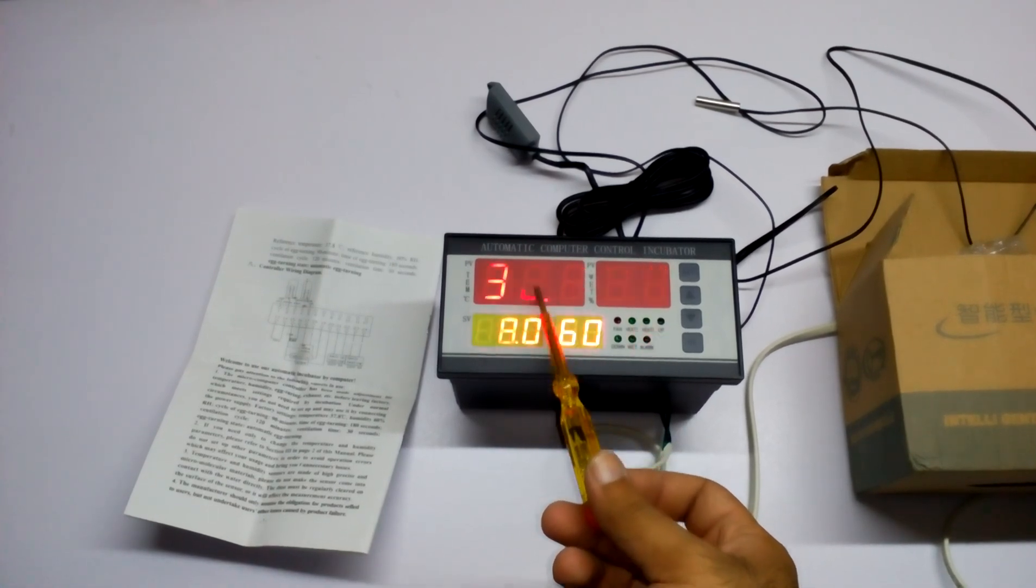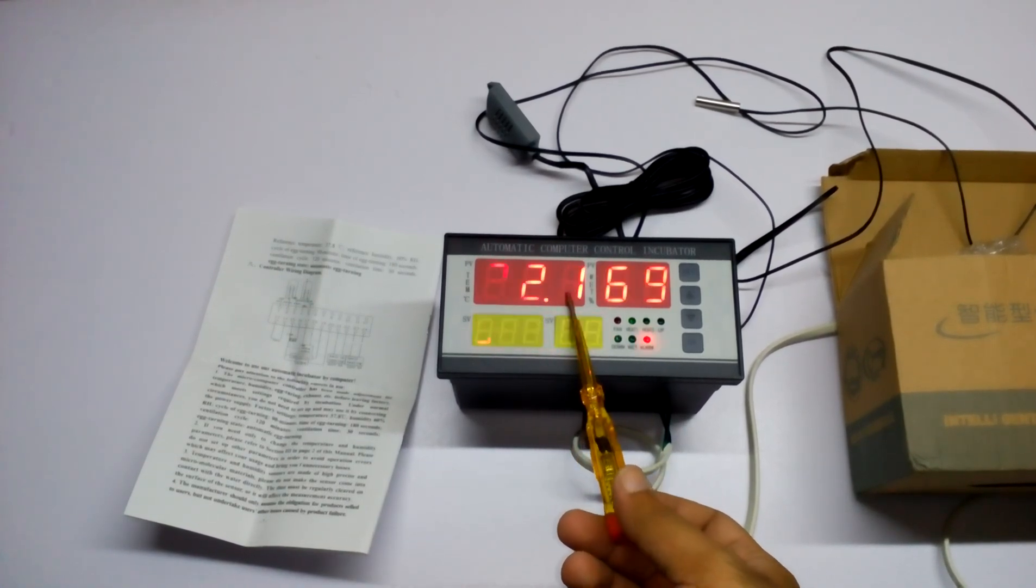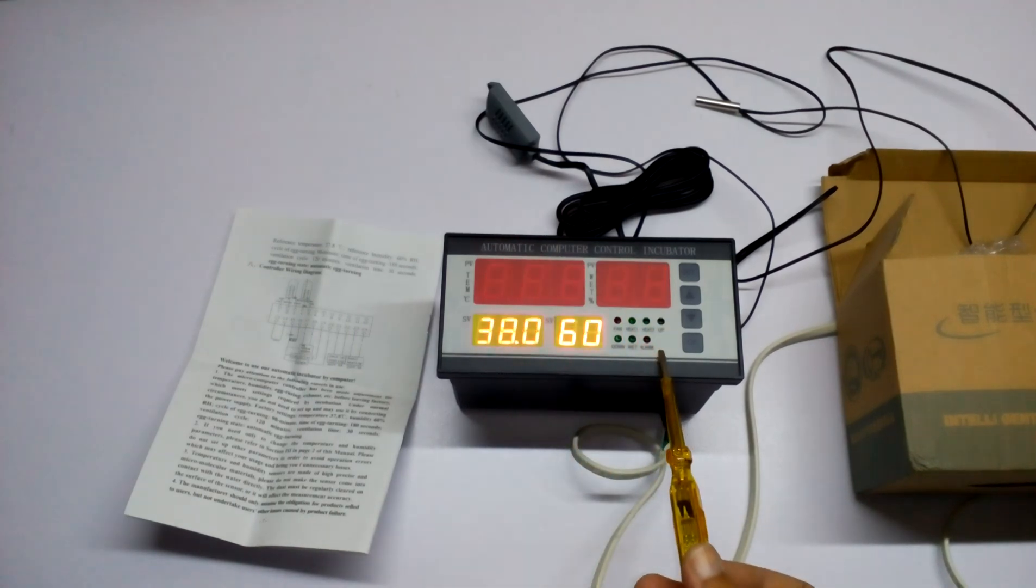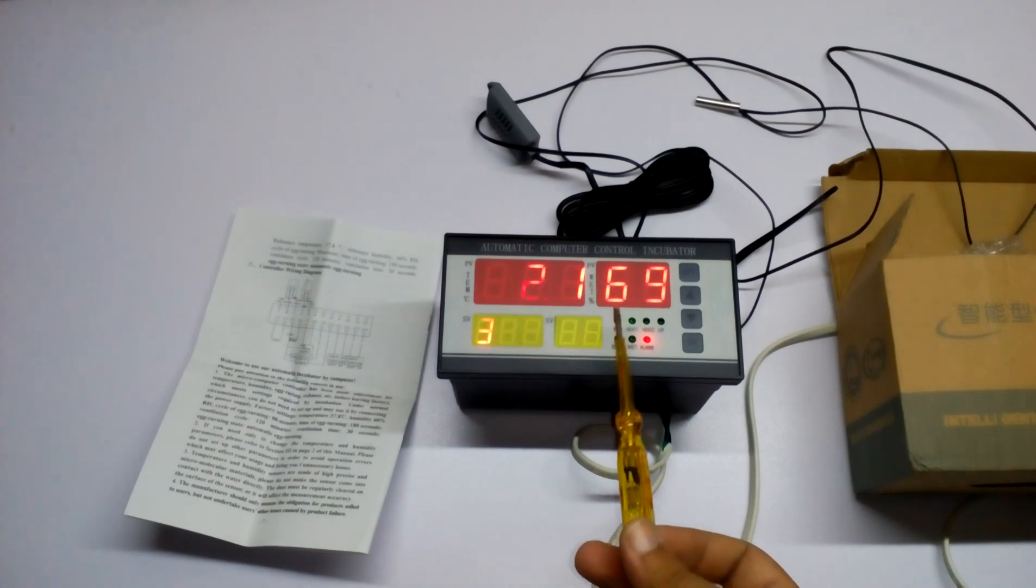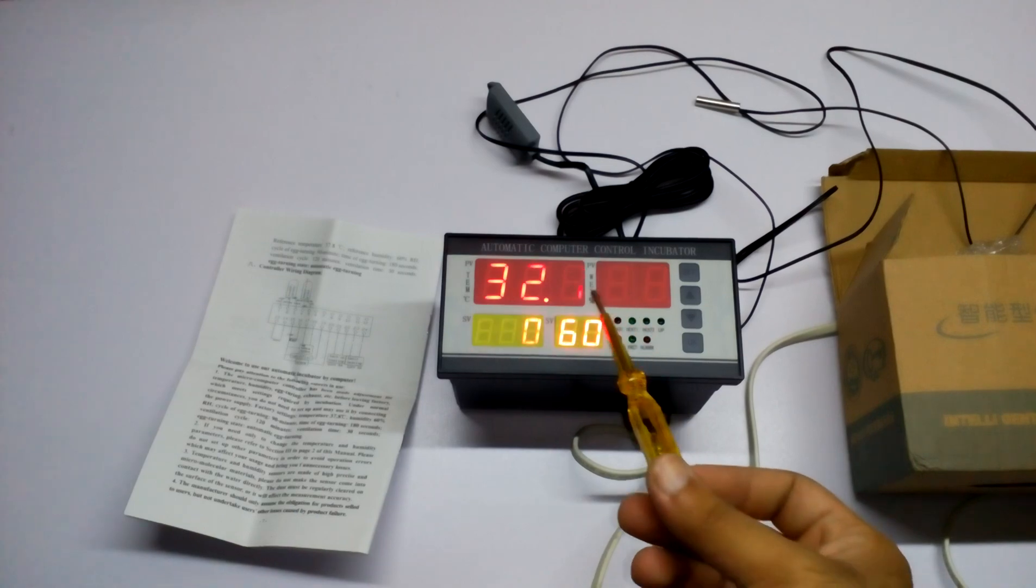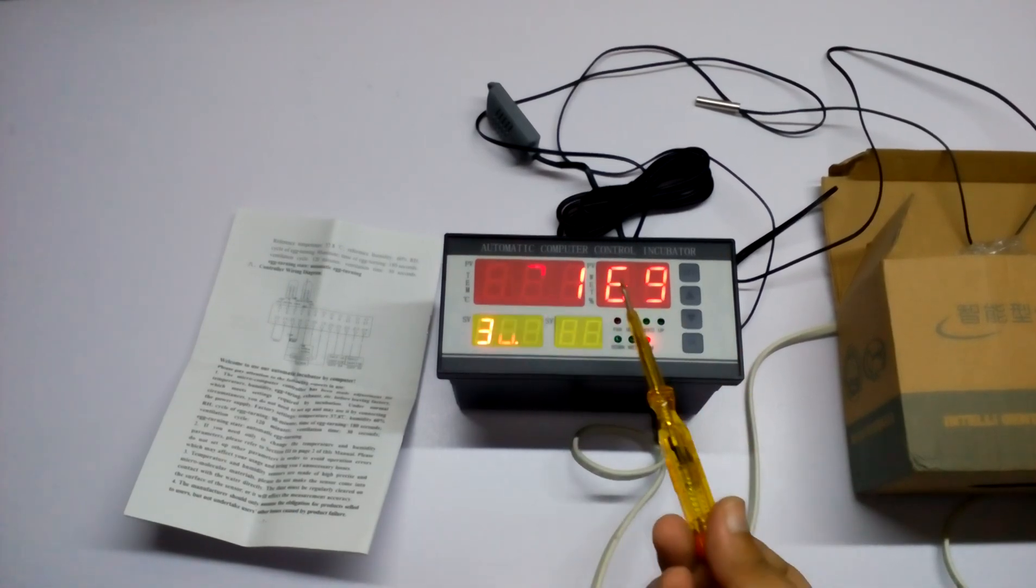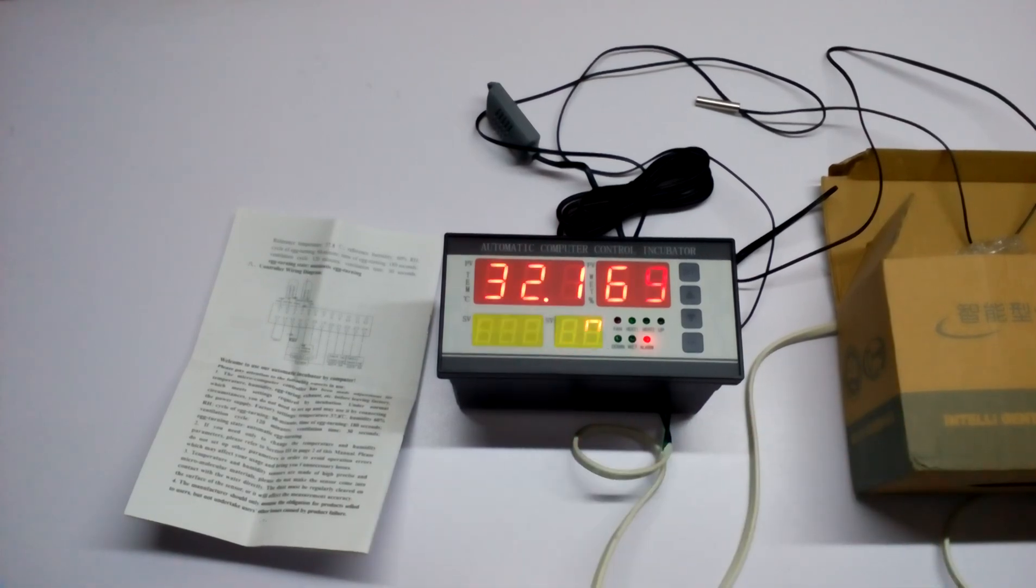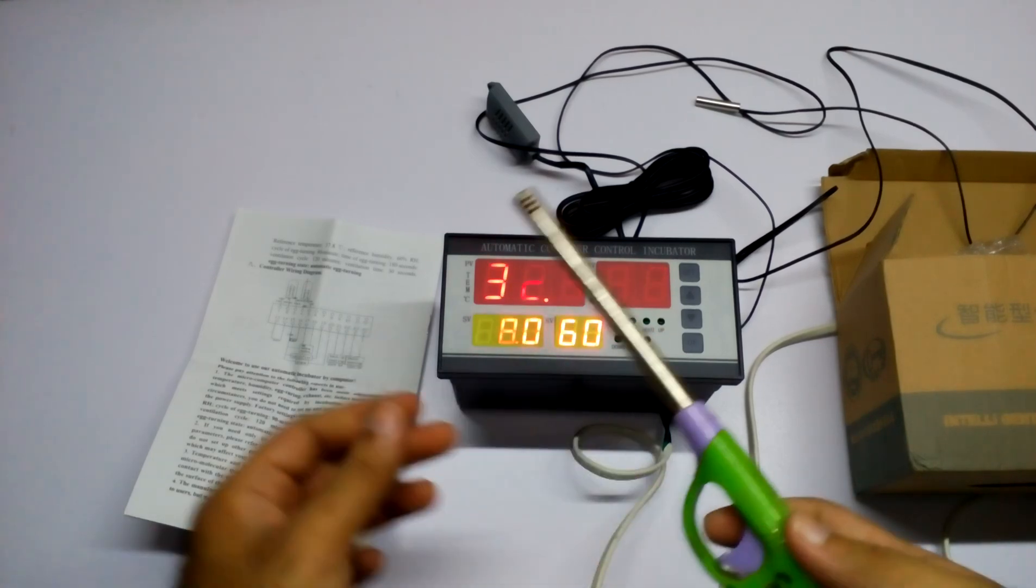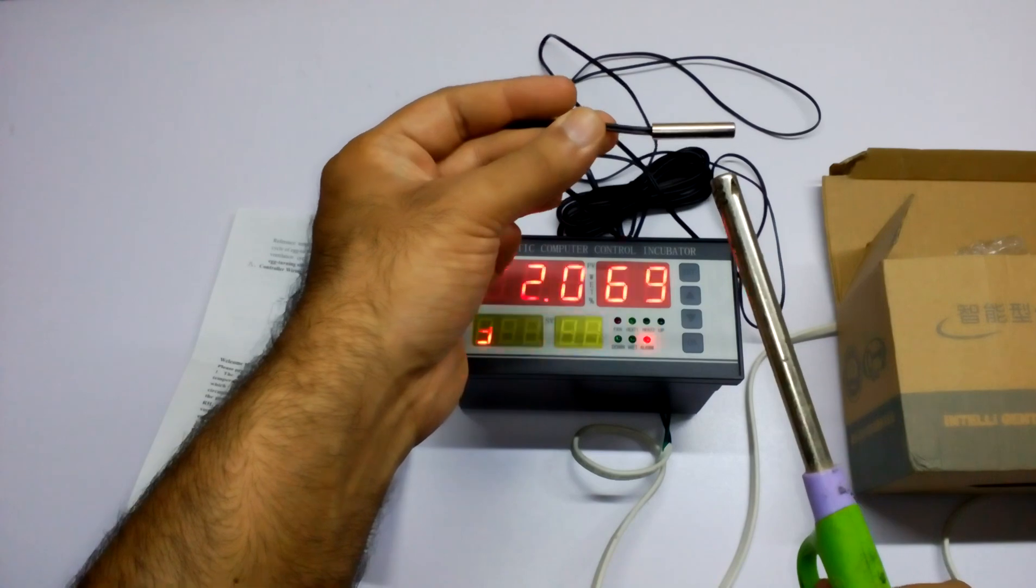As you can see, the temperature is set to 38 degrees but it's only at 32.1, so it's not reaching the setpoint and it's going to alarm. The humidity is set to 60 but it's at 69, so it's also alarming. If there is any error or some things are not working, it's going to alarm all the time until you get to the point where it works perfectly. So for a small experiment, let's see.